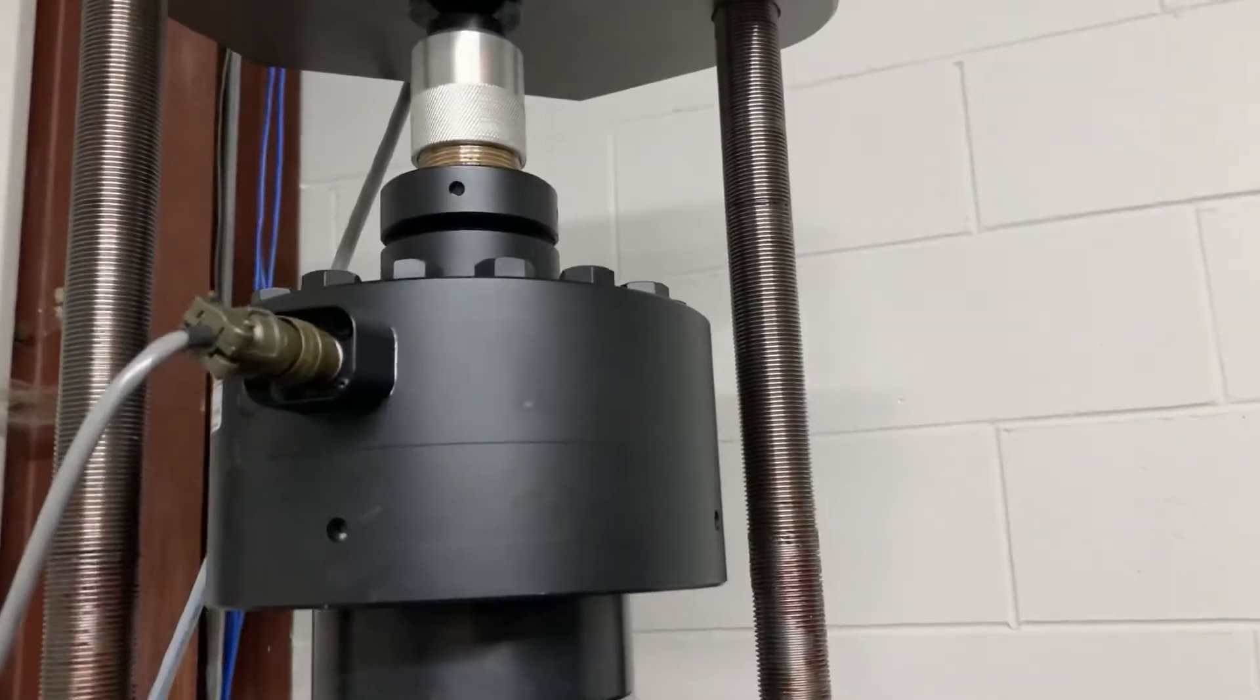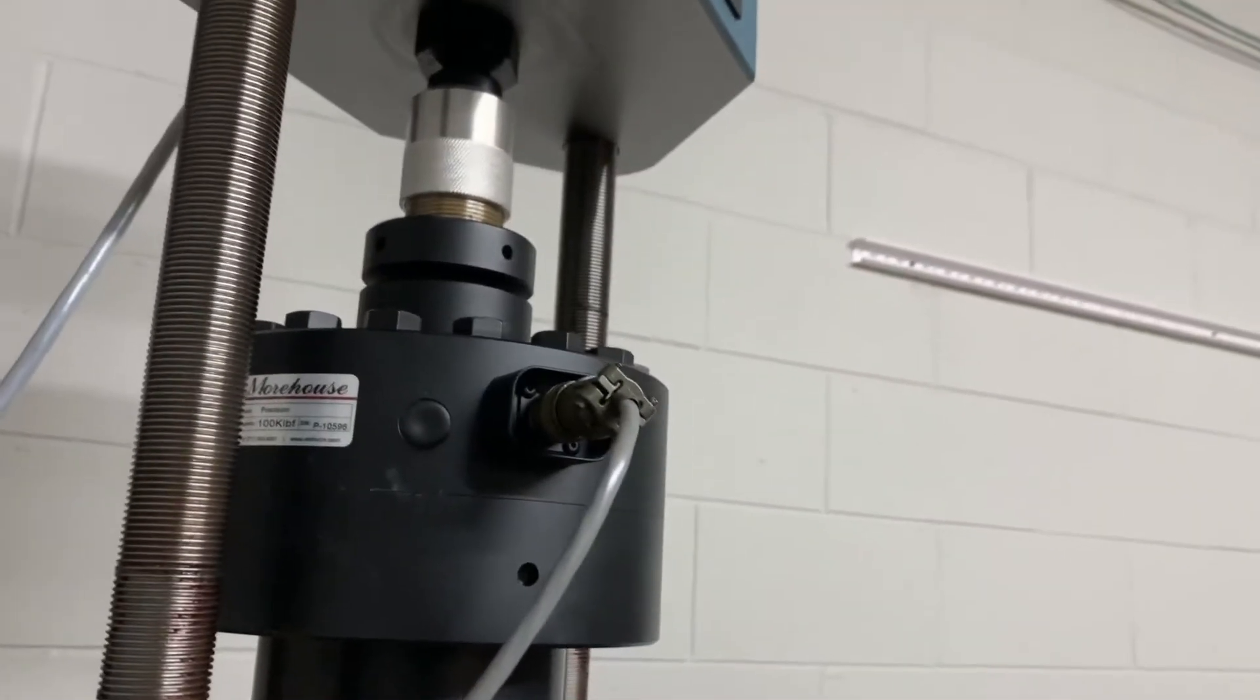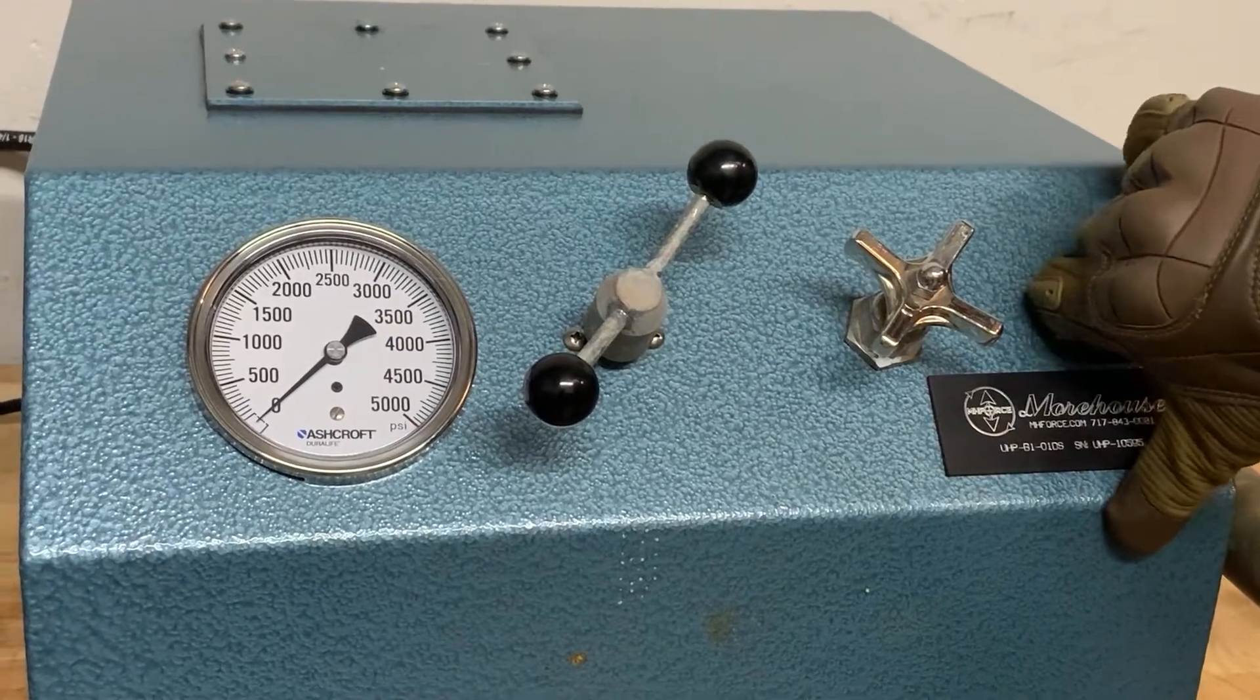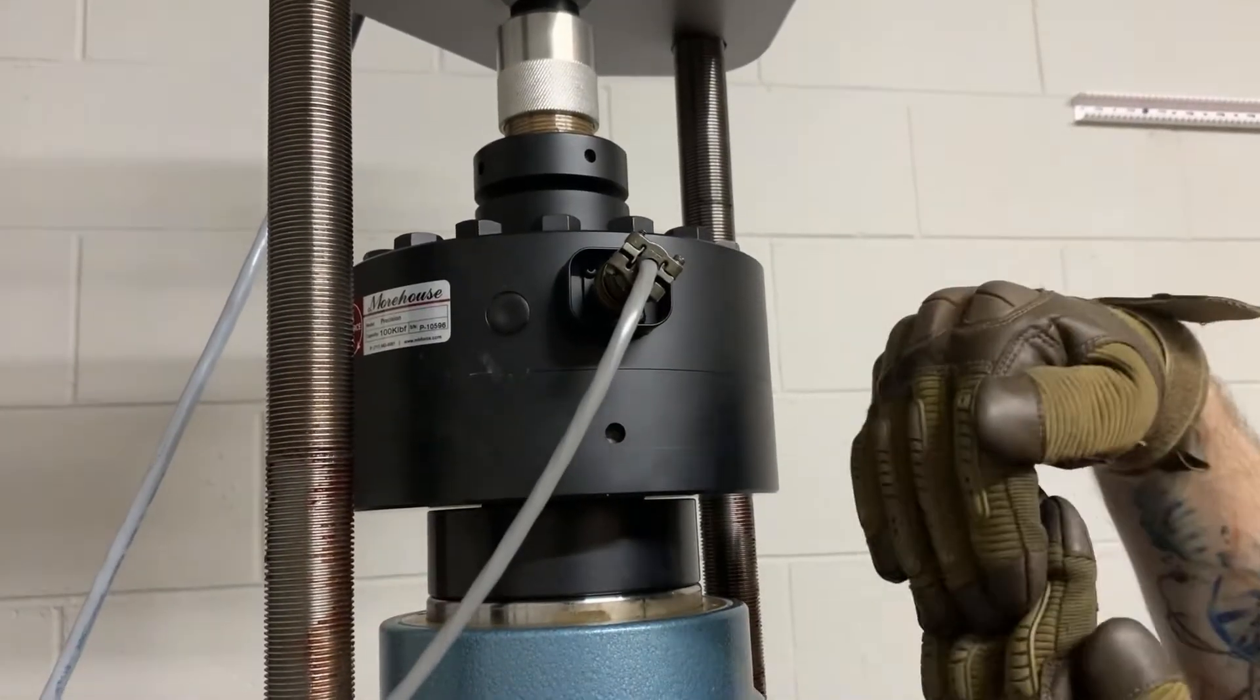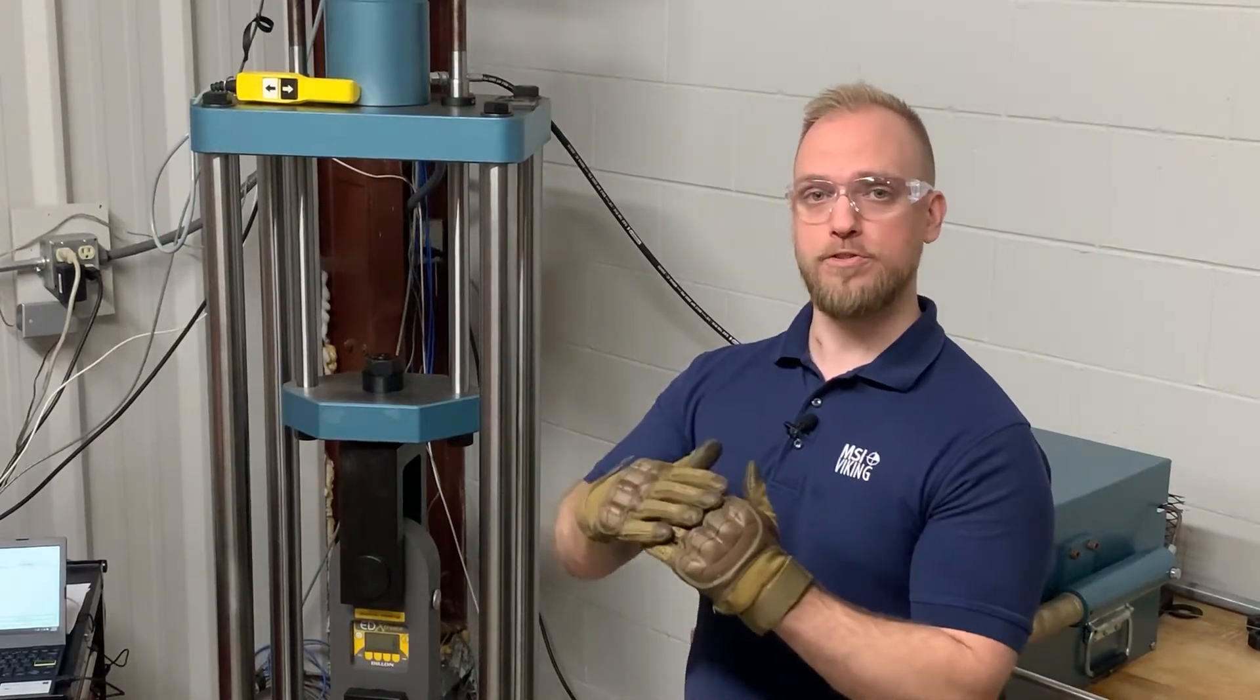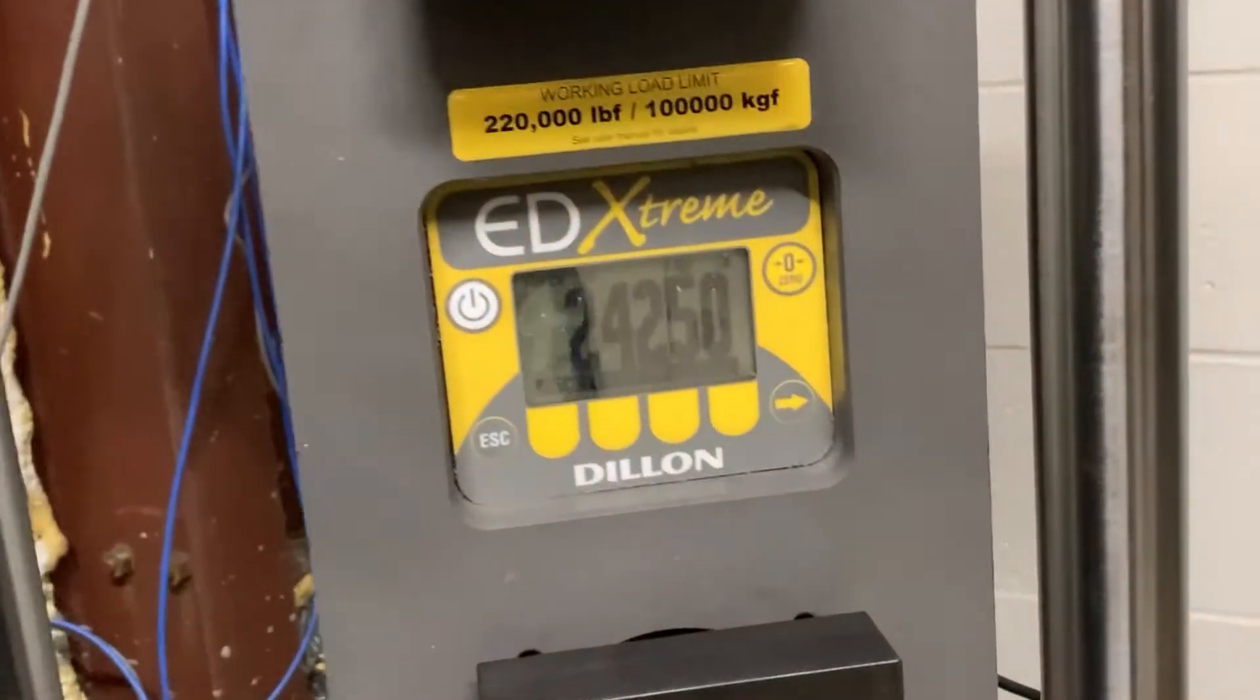Basic fundamentals of how this machine operates is you're given a reference load cell that's put up at the top in between the upper platen and the upper yoke. How it functions and operates is off of a hydraulically driven system, otherwise known as a RAM, that compresses force onto the reference load cell, and that will provide the force that we will compare our device under test to.